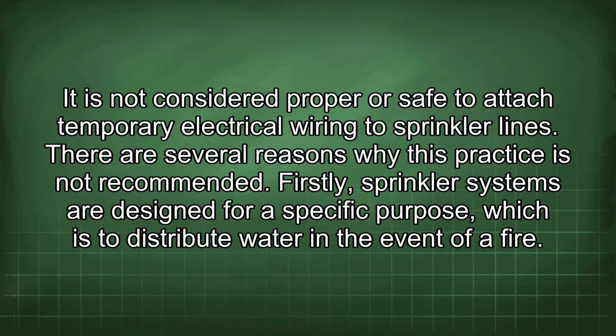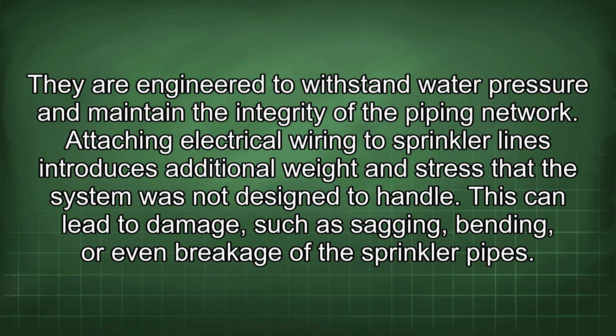It is not considered proper or safe to attach temporary electrical wiring to sprinkler lines. There are several reasons why this practice is not recommended. Firstly, sprinkler systems are designed for a specific purpose, which is to distribute water in the event of a fire. They are engineered to withstand water pressure and maintain the integrity of the piping network. Attaching electrical wiring to sprinkler lines introduces additional weight and stress that the system was not designed to handle. This can lead to damage such as sagging, bending, or even breakage of the sprinkler pipes.